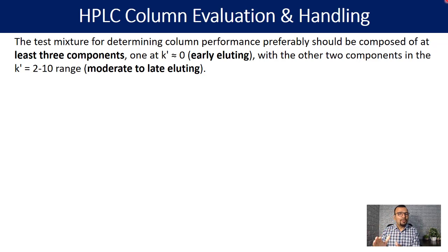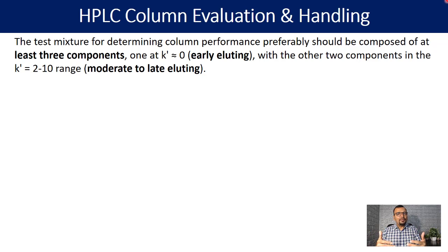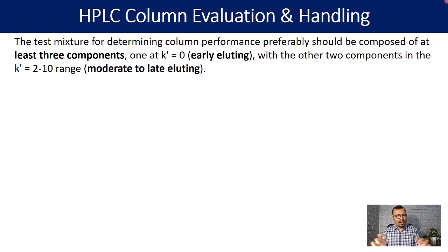If you only select one component which is, let's say, late eluting, but the column has a problem with the early eluting compound, then you are going to miss the column issues with those early eluting compounds. For that reason, having compounds eluting across the chromatography — late eluting, mid eluting, and early eluting — is important.